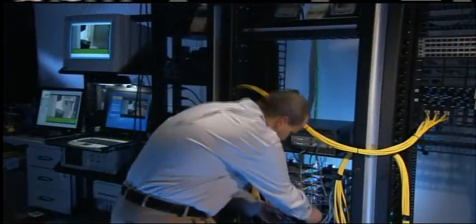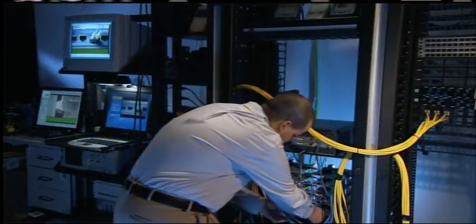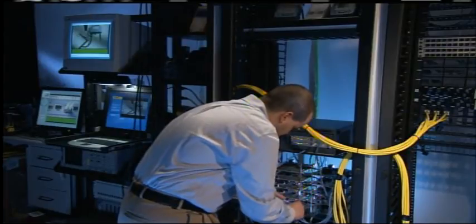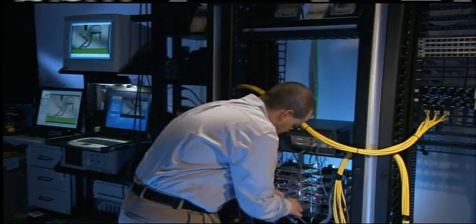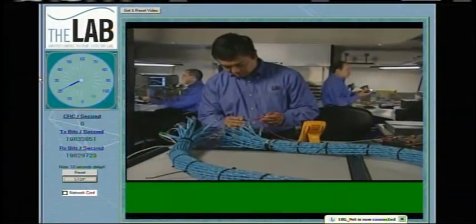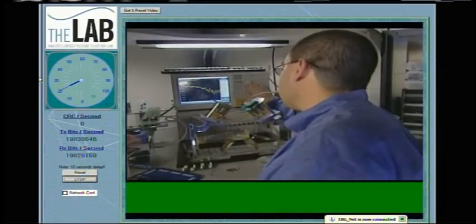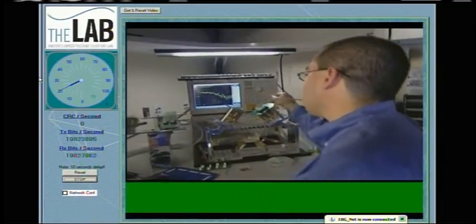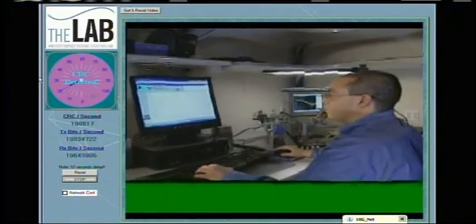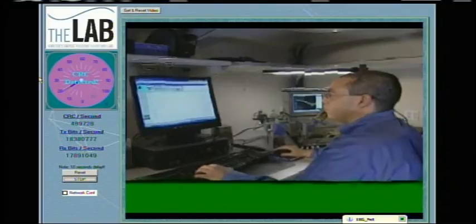We'll do this same test again, except this time, instead of just running test data through the disturbed channel, we'll run a video signal. Again, we'll start with the CAT 6 channel and start adding the disturber channels. We only get to four disturbers before the video signal completely locks up.